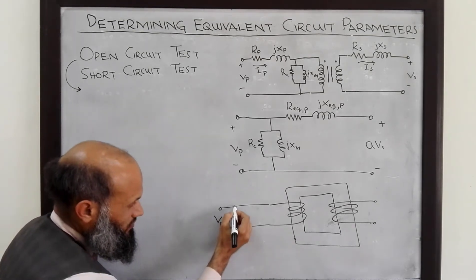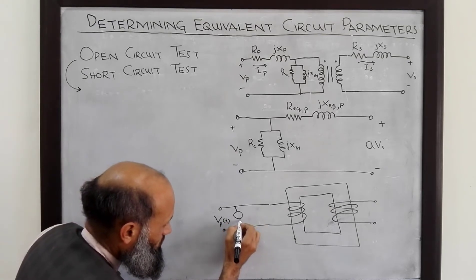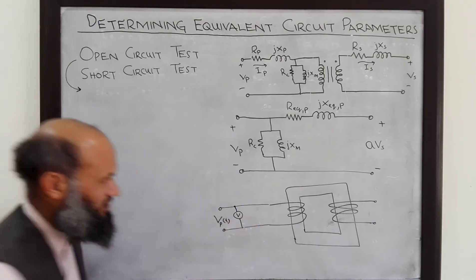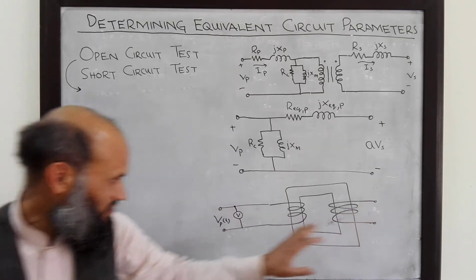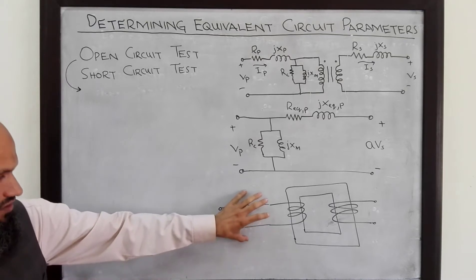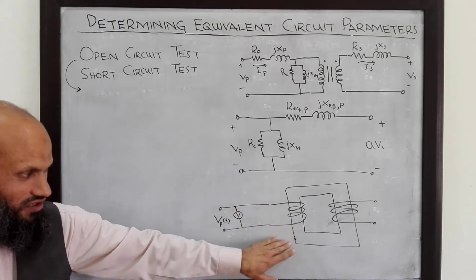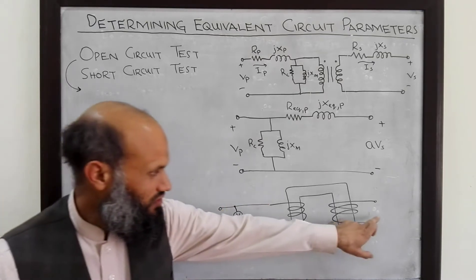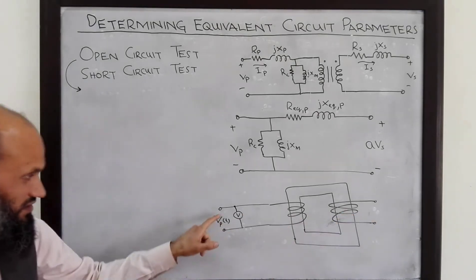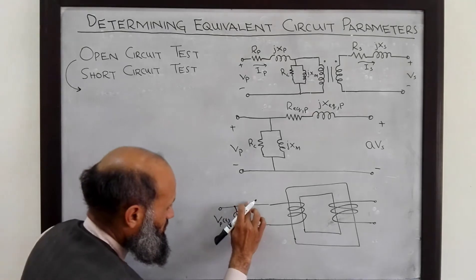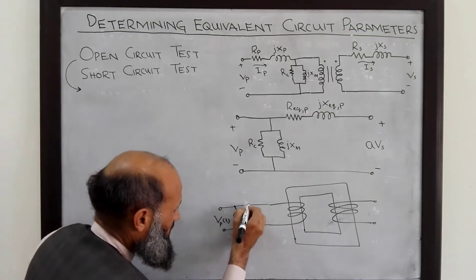We measure the applied voltage using a voltmeter. Ideally, if the secondary is open circuited, no primary current should flow. However, this is not an ideal transformer, so even with the secondary open circuited some current will flow on the primary. We also measure this primary current using an ammeter.